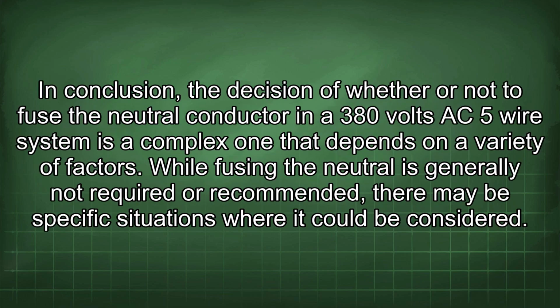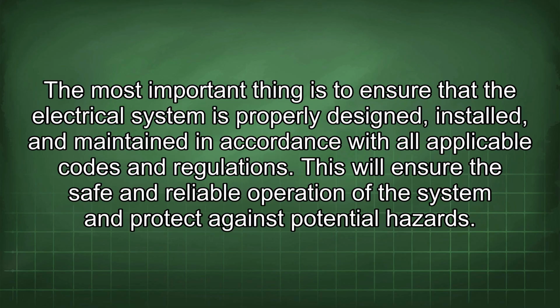In conclusion, the decision of whether or not to fuse the neutral conductor in a 380-volt AC 5-wire system is a complex one that depends on a variety of factors. While fusing the neutral is generally not required or recommended, there may be specific situations where it could be considered. The most important thing is to ensure that the electrical system is properly designed, installed, and maintained in accordance with all applicable codes and regulations. This will ensure the safe and reliable operation of the system and protect against potential hazards.